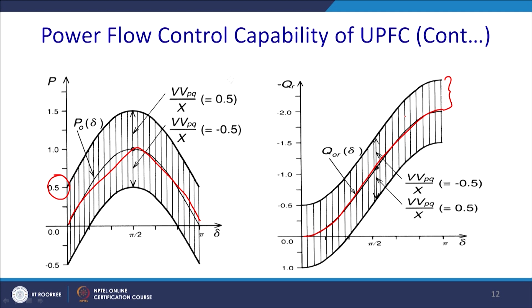Now, the phasor diagram defines the relationship of Vs, Vr, Vx, the voltage phasors, with x and the inserted phasor V_pq. Essentially this is your receiving end voltage and this was your sending end voltage, and you have injected this voltage V_pq, thus effectively this becomes a new voltage, that is V effective sending, and thus there will be a new delta. So, the inserted voltage phasor V_pq is added at a fixed angle. The phasor Vs produces the effective sending end voltage, that is Vs effective, given by Vs plus V_pq.